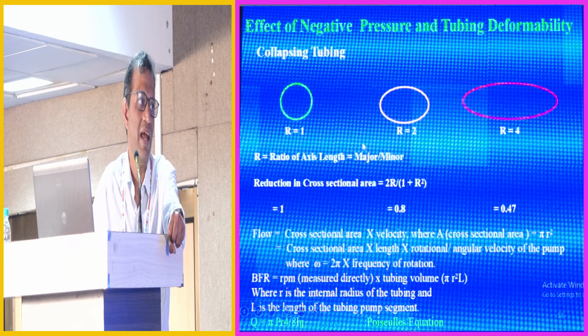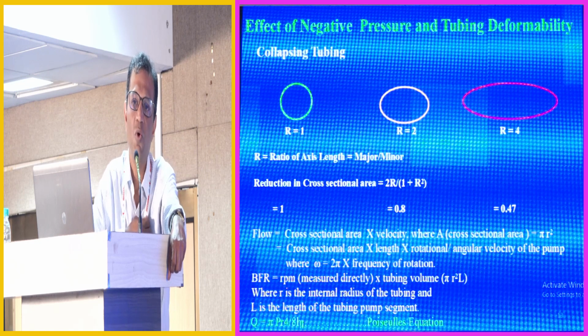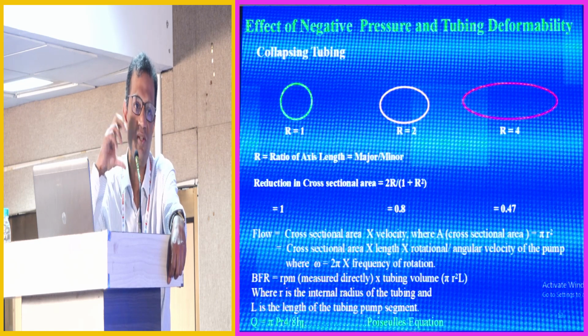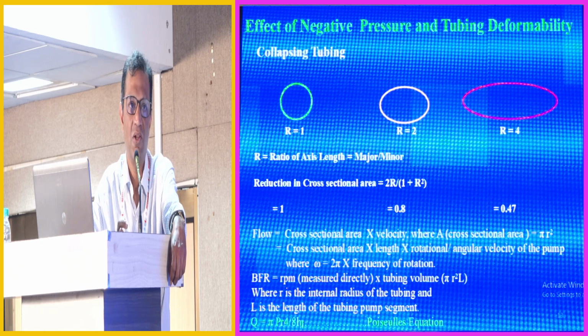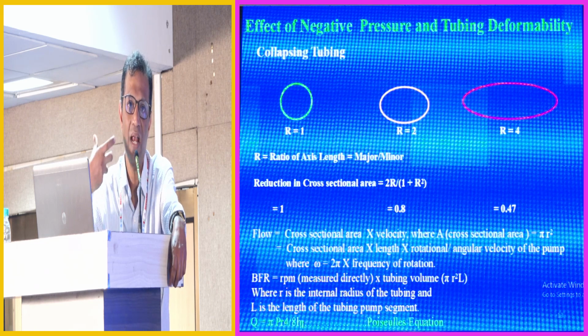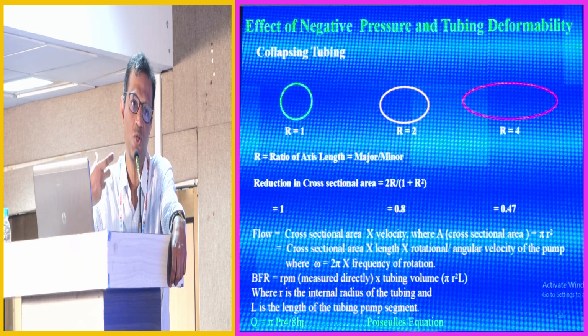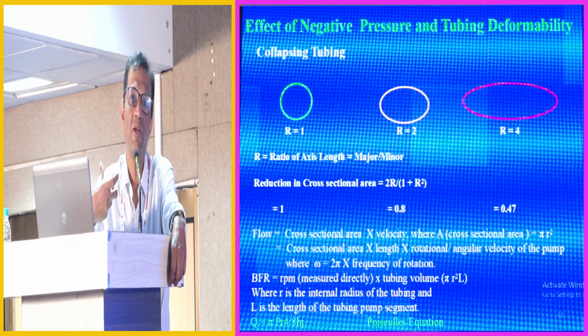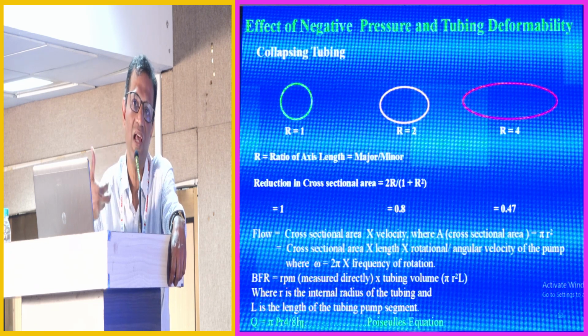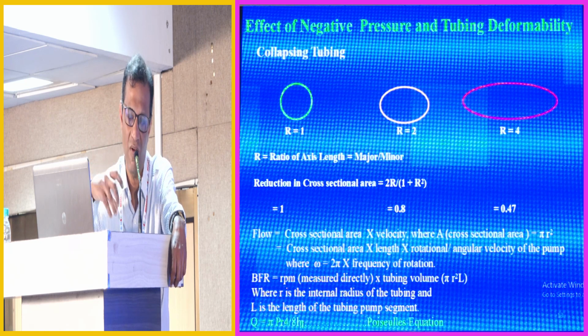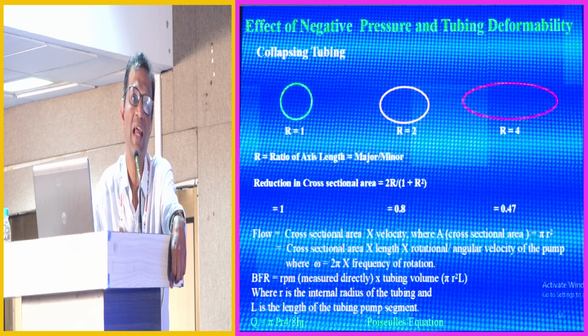The tubing gets stretched, it gets converted from a circular cross section to an elliptical one. And as we know, an ellipse has 2 axes. Now, the consequence of this is that the cross-sectional area will decrease in proportion to the ratio of the lengths of the axis. So the greater the ellipse's long axis to short axis ratio, the less the cross-sectional area will be. And since cross-sectional area times rotation times velocity of the pump is equal to blood flow, as the tubing gets stretched, it actually will deliver a lower blood flow.